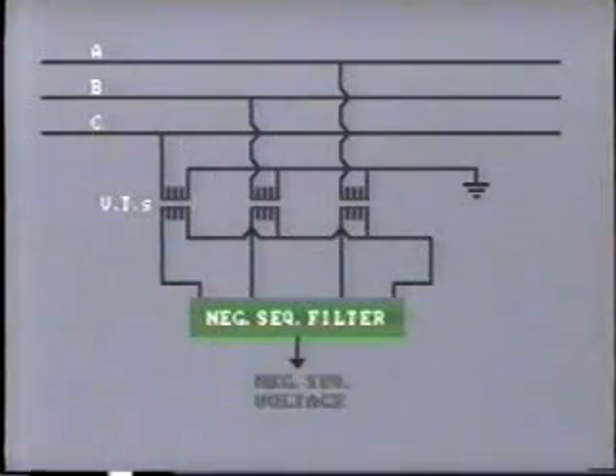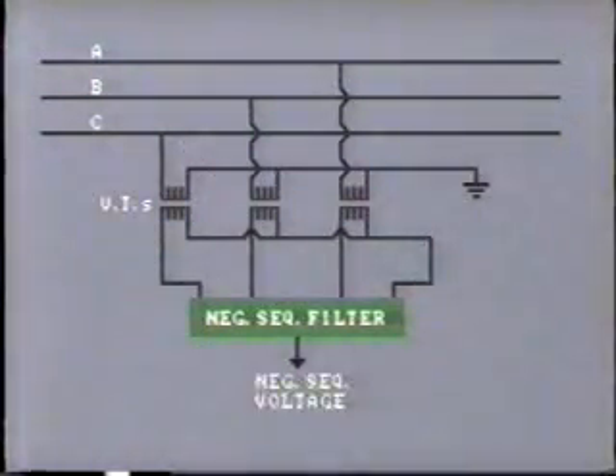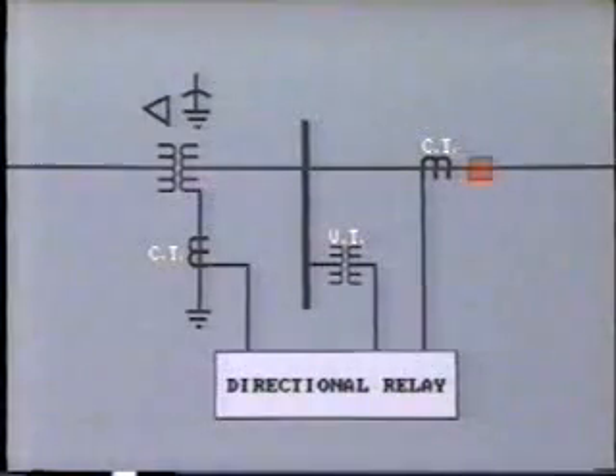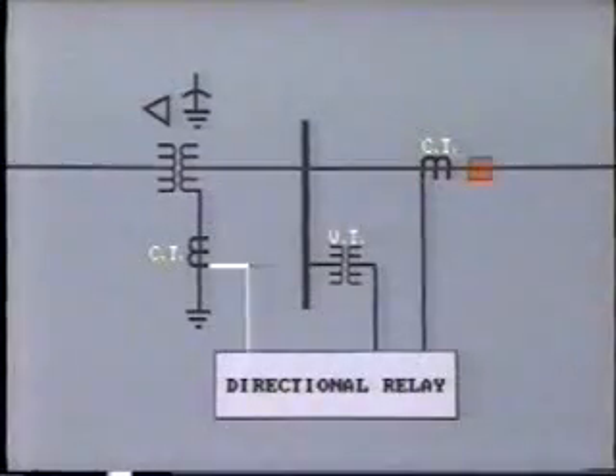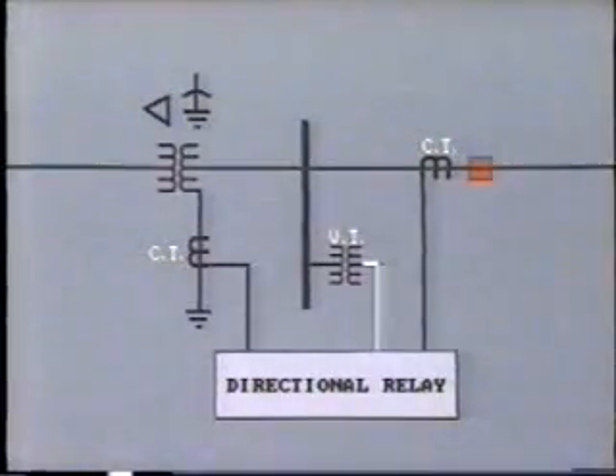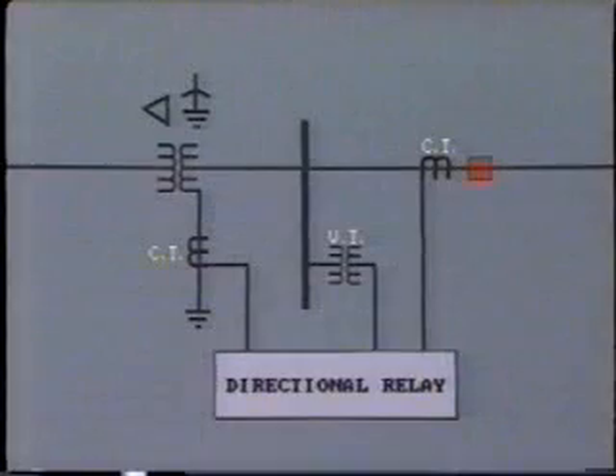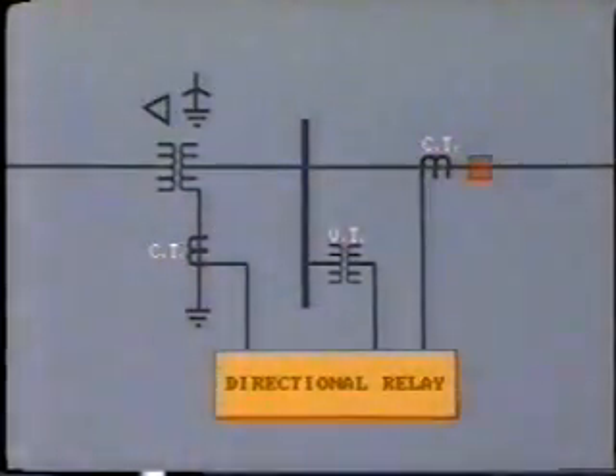The negative sequence voltage is obtained from VTs and by connecting the appropriate filter circuit to the relay. Because of the vital importance of polarization in the operation of directional elements, many ground relays are polarized from 2 sources. In this arrangement, there are 2 separate directional elements, one polarized by current and one by voltage. These elements operate in parallel so that either one can release, that is, permit the overcurrent relay to operate.